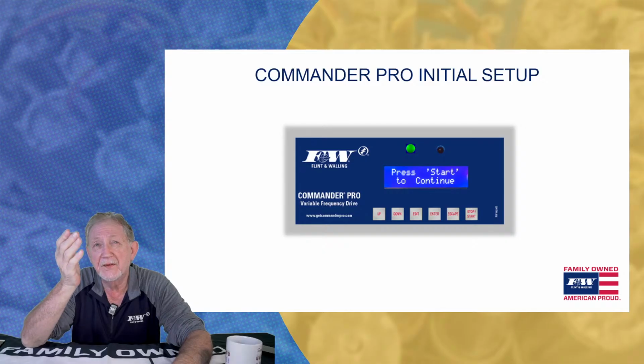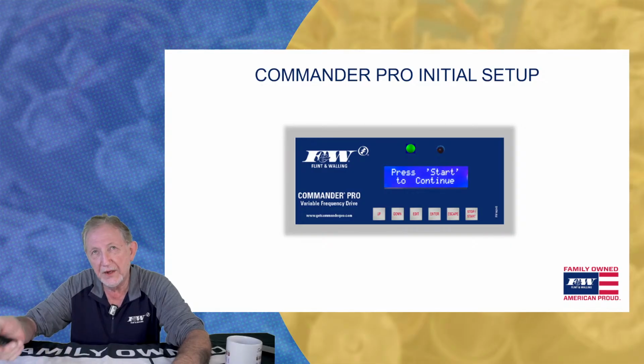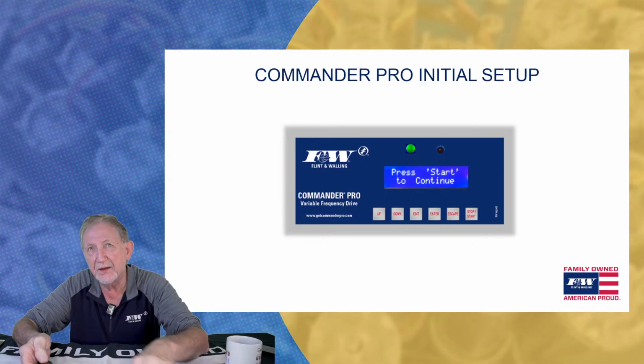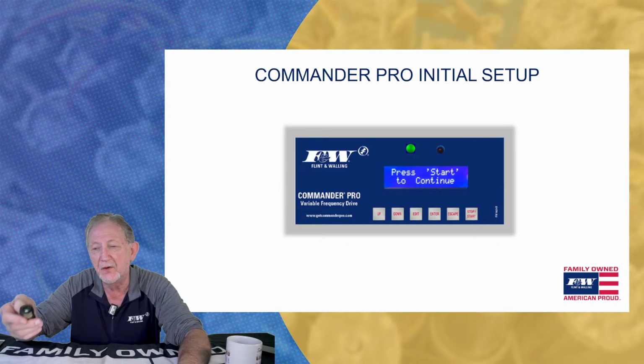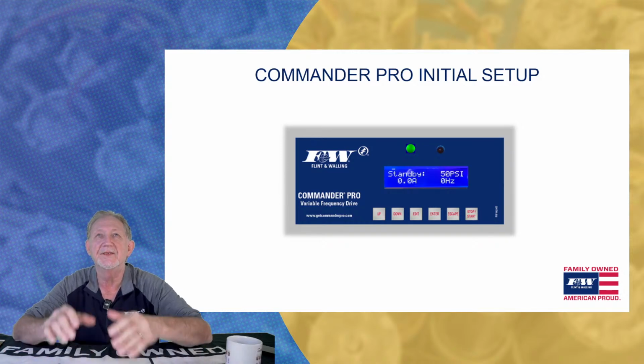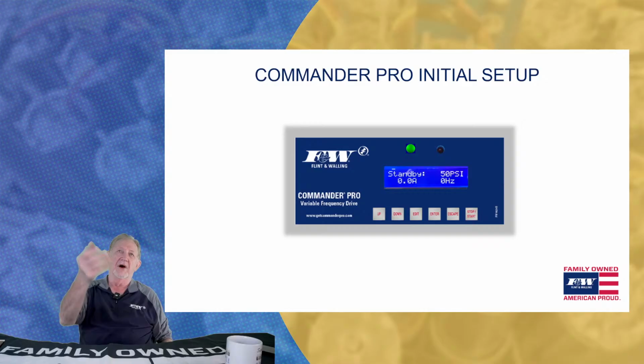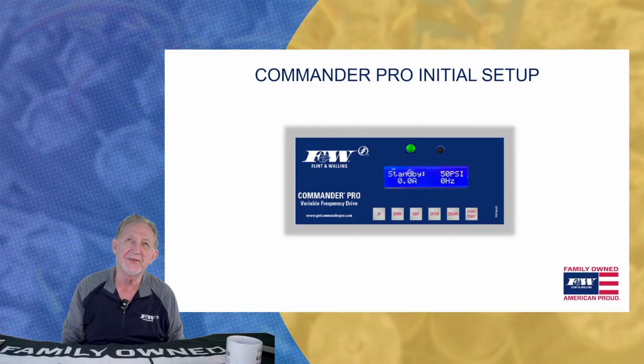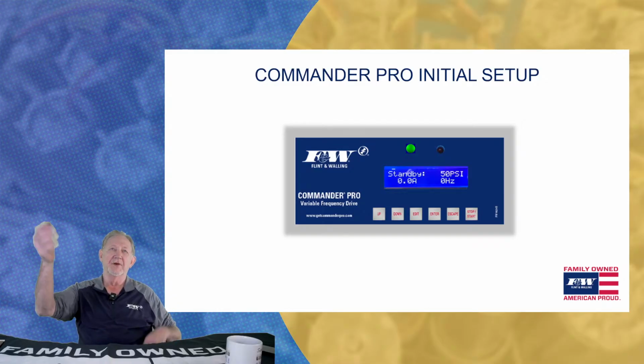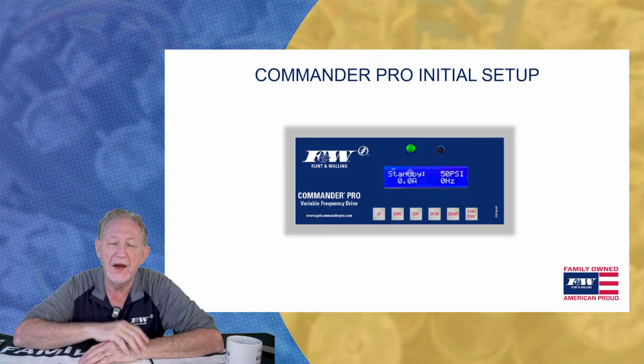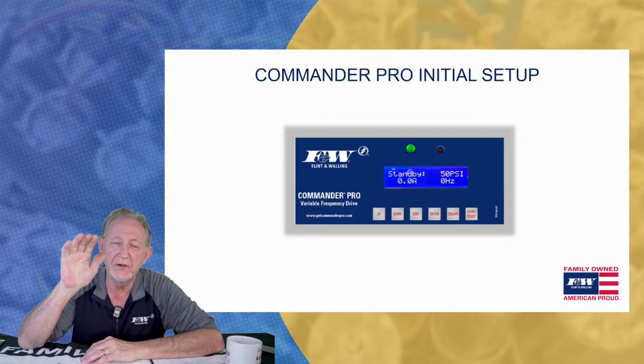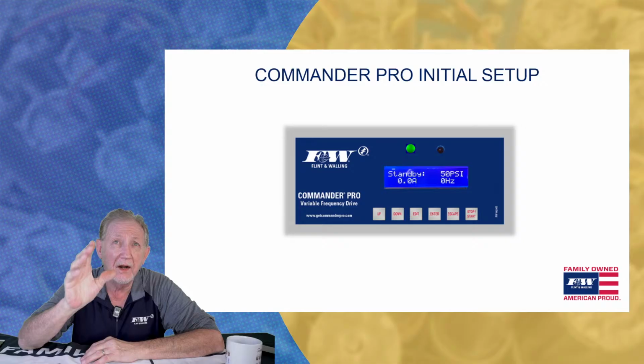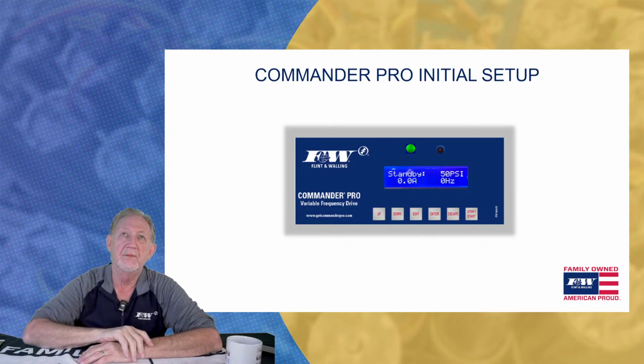But once you get through that startup menu, it's going to say press start to continue. When you press that start button, that far right button over there, here's the display now. It's in standby. We've got our pressure set point at 50 psi. No amps, no hertz. That drive's now in standby. That initial quick start has gone away. We've programmed it in here.